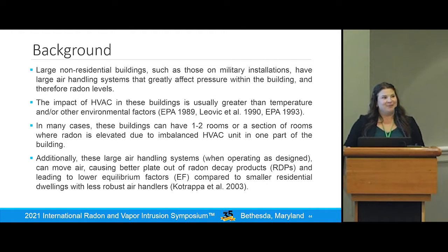If the HVAC is working properly and has forced air, then that building is going to be under positive pressure, and that's going to deter radon gas from entering into the building. Alternatively, if that HVAC is not working properly, you can have negative pressure in the building, and that's going to draw radon gas into the building. The impact of HVAC in these buildings is usually greater than temperature and or other environmental factors such as wind or rain. And in many cases, these buildings can have one or two rooms that are elevated, or a section of rooms, and this is most likely due to having an imbalanced HVAC unit.